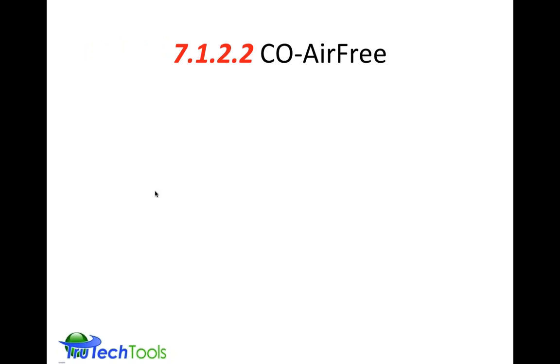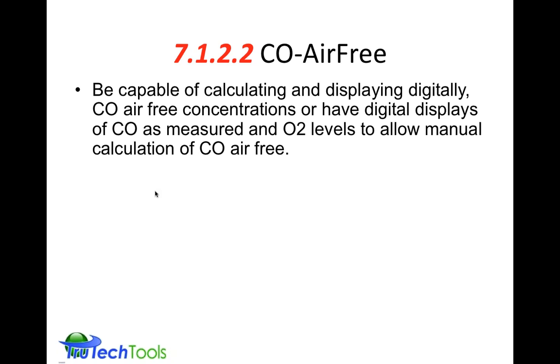That element that rules them out is the next topic we're talking about here, which is CO air-free. So the device that you use for CO air-free testing must be capable of calculating and displaying digitally the CO air-free concentration, or have displays of O2 and CO such that you could do a manual calculation of CO air-free. That last part of the sentence usually is never employed because most people do have combustion analyzers which measure the CO and the O2, so they're able to get that calculation. It's done digitally by the device itself.